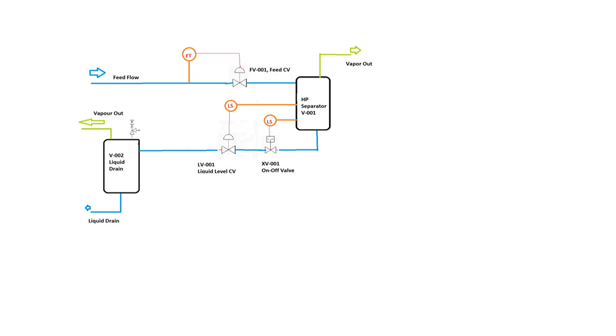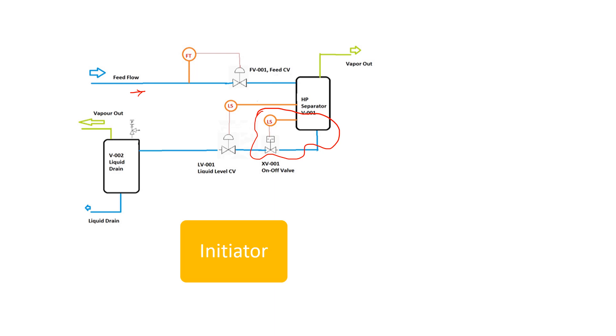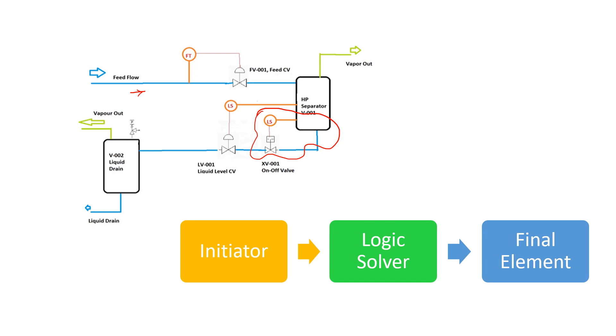As a recap, this is an HP separator where feed flow comes in and goes to drain. The critical level of the HP separator — if it goes high, it will overflow and incidents can occur. The safety loop consists of an initiator, a logic solver, and a final element. The initiator is a level switch, the logic solver is a safety PLC, and the final element is an on/off valve — all in one-out-of-one configuration.